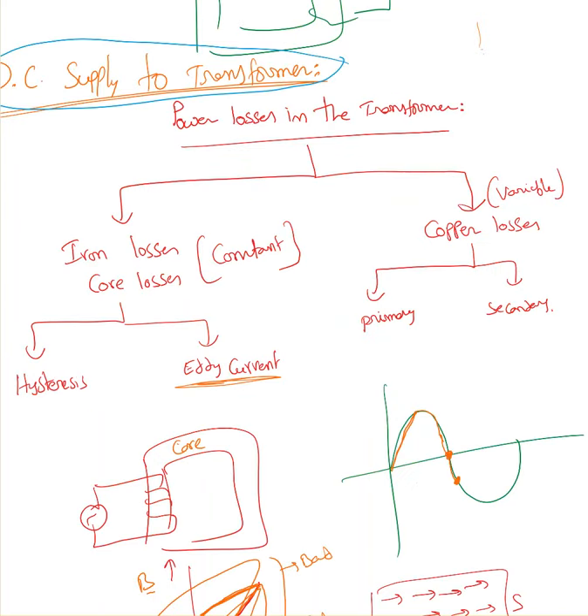Now we're going to talk about practical transformers. In a practical transformer, there are always power losses, of two types. One is iron losses, also called core losses. These are constant losses - it doesn't matter if you connect zero load to the transformer, as long as there is power supply, there are always iron losses.